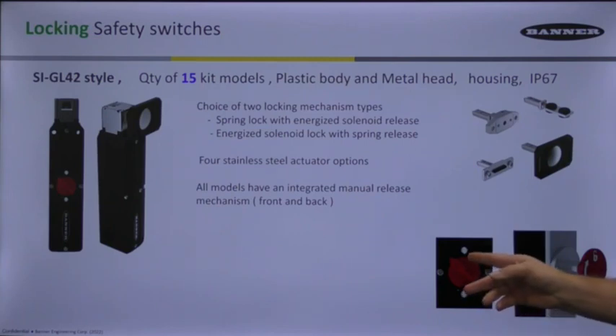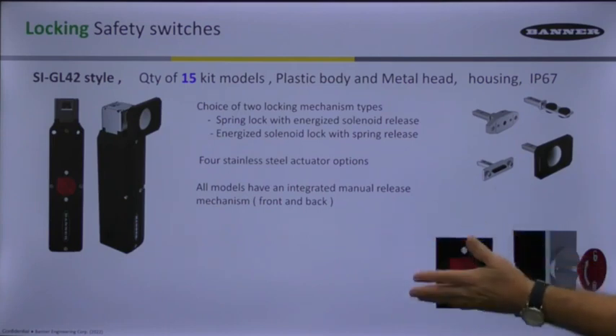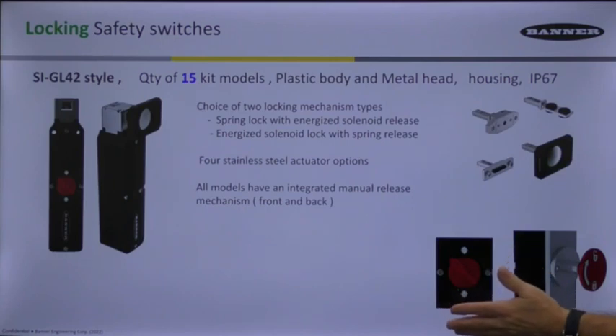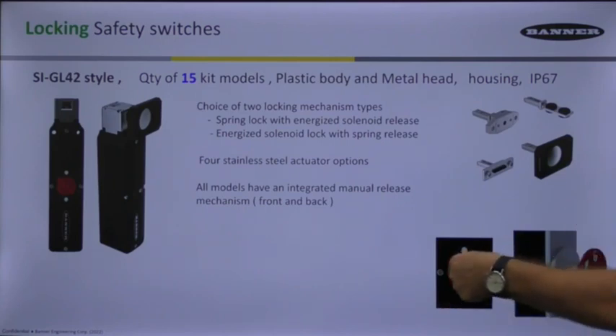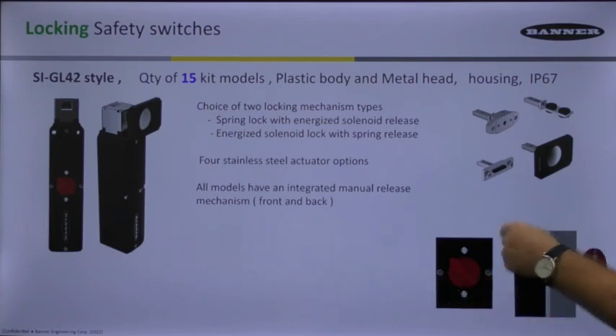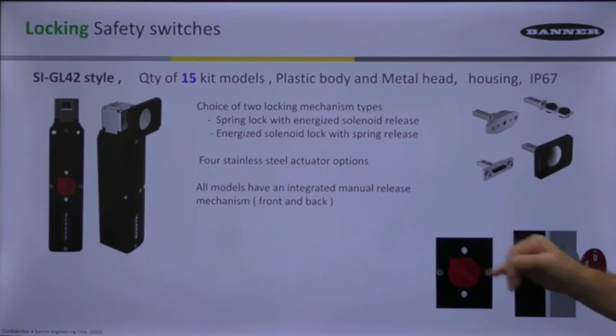It's not as easy as just simply unlocking and locking, because typically the voltage coming to the coil is already going to carry out that function. It's just in the case of emergency that you need to get in there. And if you did unlock it, it takes a special tool to set it back for the run position, so there will probably be somebody in charge of gaining access to that switch because they have the key that matches the setup on that assembly.